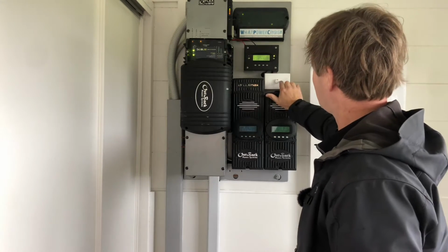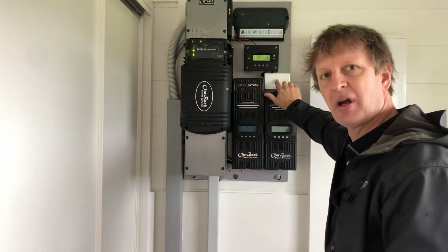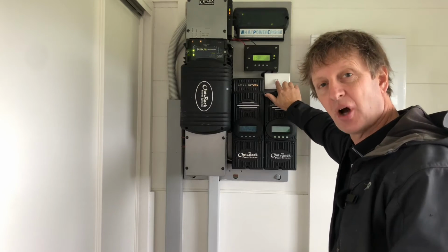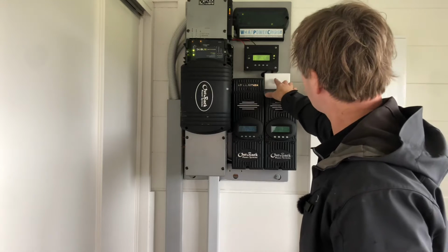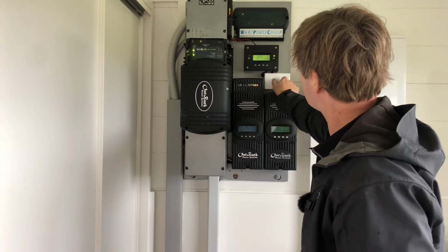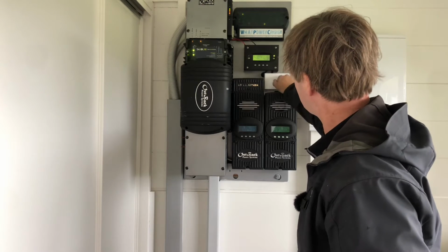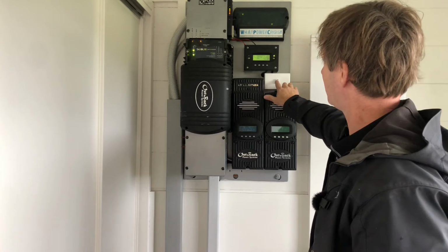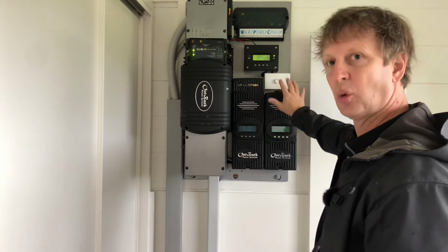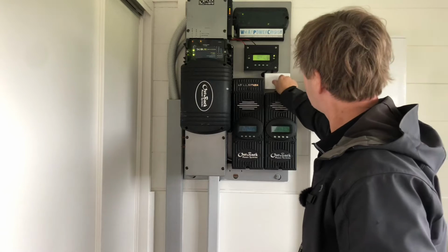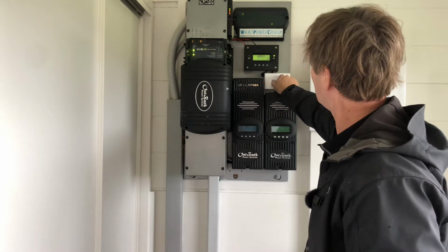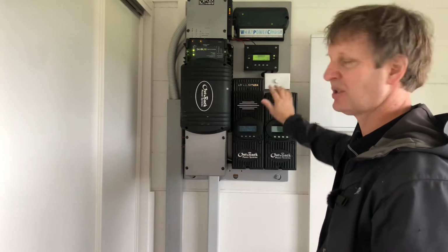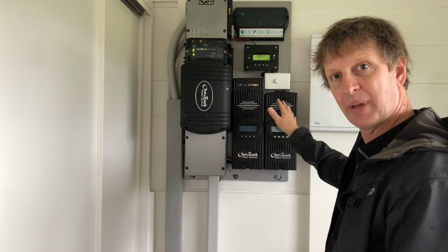This is a generator control switch. The generator is automatic start and stop, and with the little U shape of that switch, it's a rotary switch that can be turned. The U shape up with the A showing is auto, and the U shape to the left or right is off, so the generator will not start on automatic.